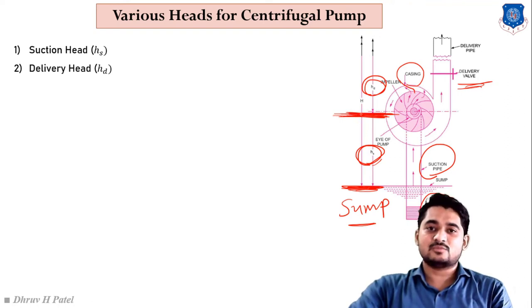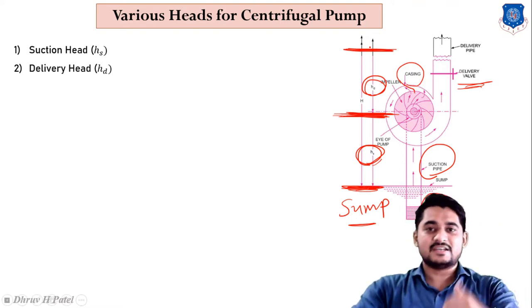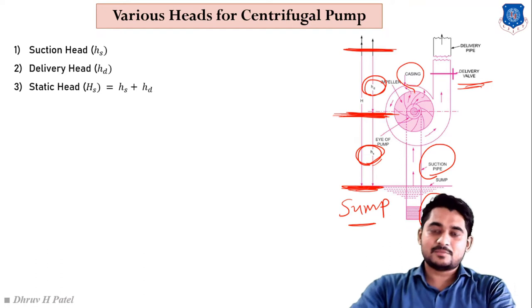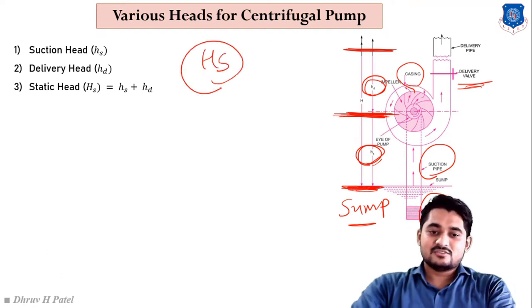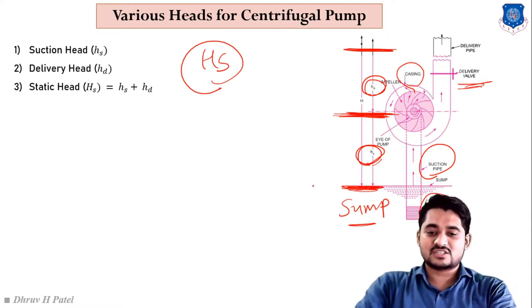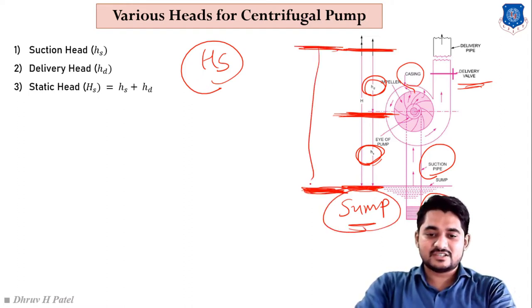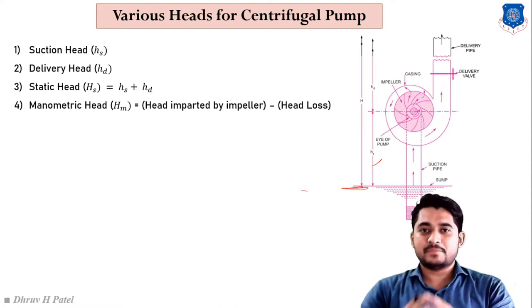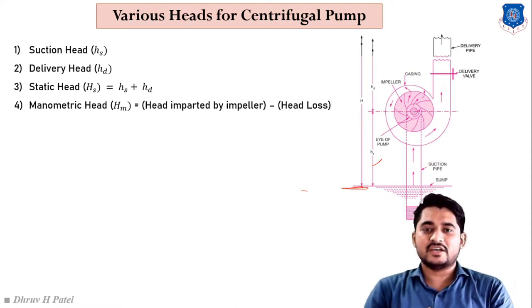Then static head, represented by capital H_s, is basically suction head plus delivery head — the summation of these two. If we take the distance from our sump level to our final destination level, that is known as static head. Next is manometric head, which is very important regarding the centrifugal pump.